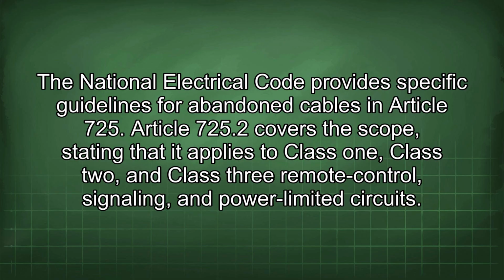The National Electrical Code provides specific guidelines for abandoned cables in Article 725. Article 725.2 covers the scope, stating that it applies to Class 1, Class 2, and Class 3 remote control, signaling, and power-limited circuits.